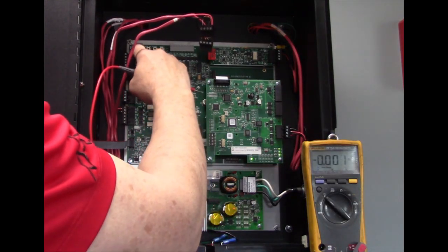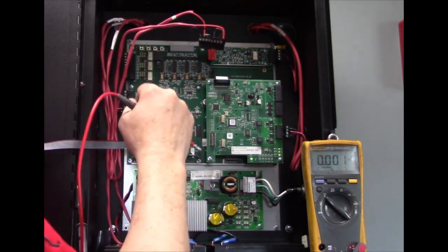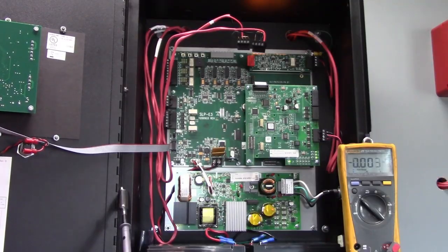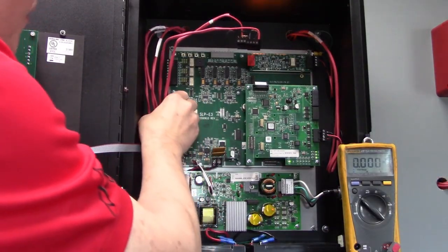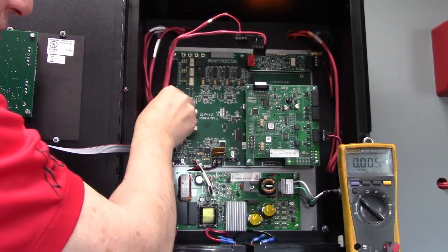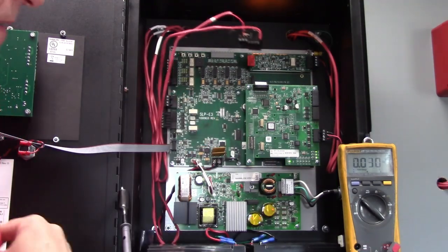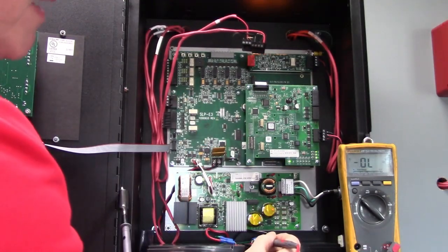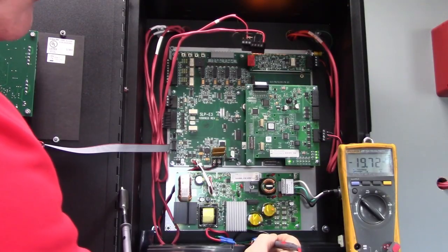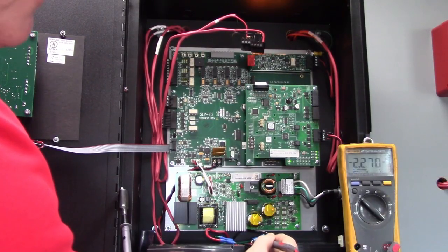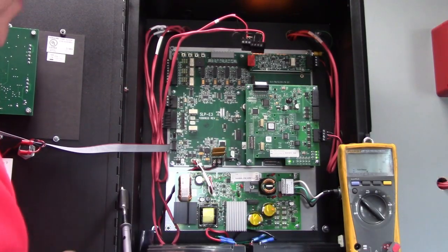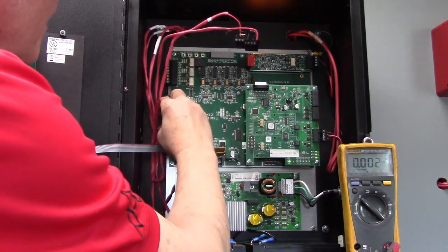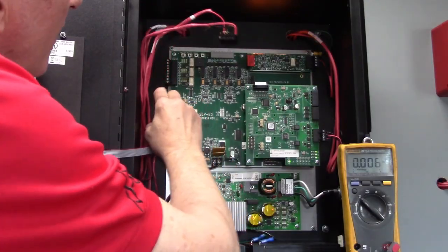Now that's in trouble. So I'm going to acknowledge the trouble. So I'm going to pull my auxiliary power off. Check my readings again. I still have about 20 volts on the negative side. So we know that's not it. That's not what is causing the problem. We're going to put these back on for now.